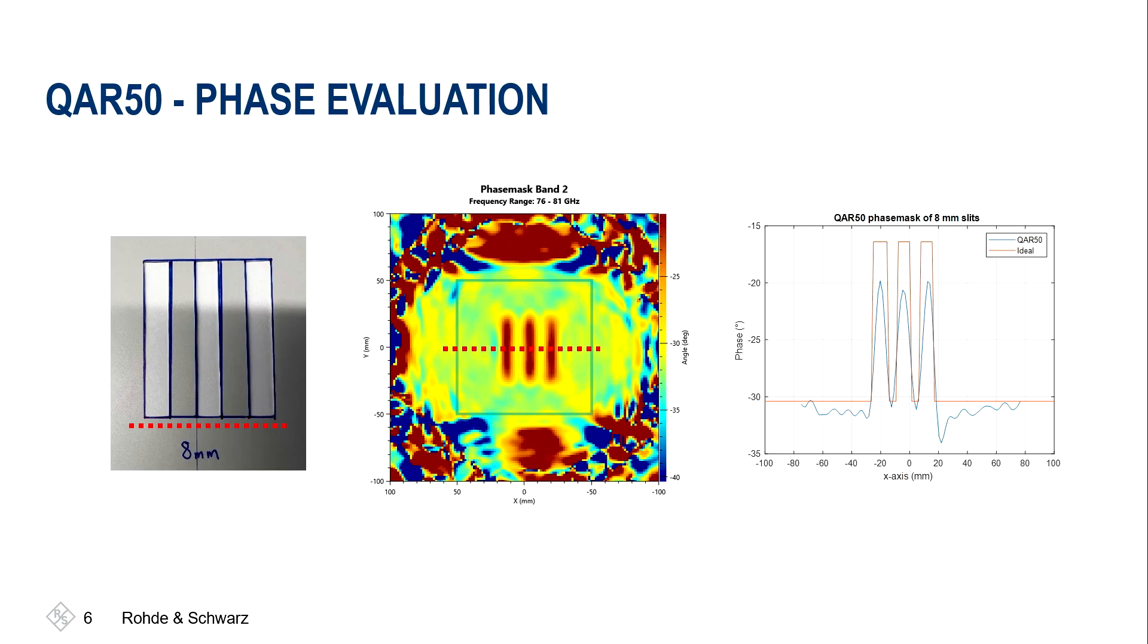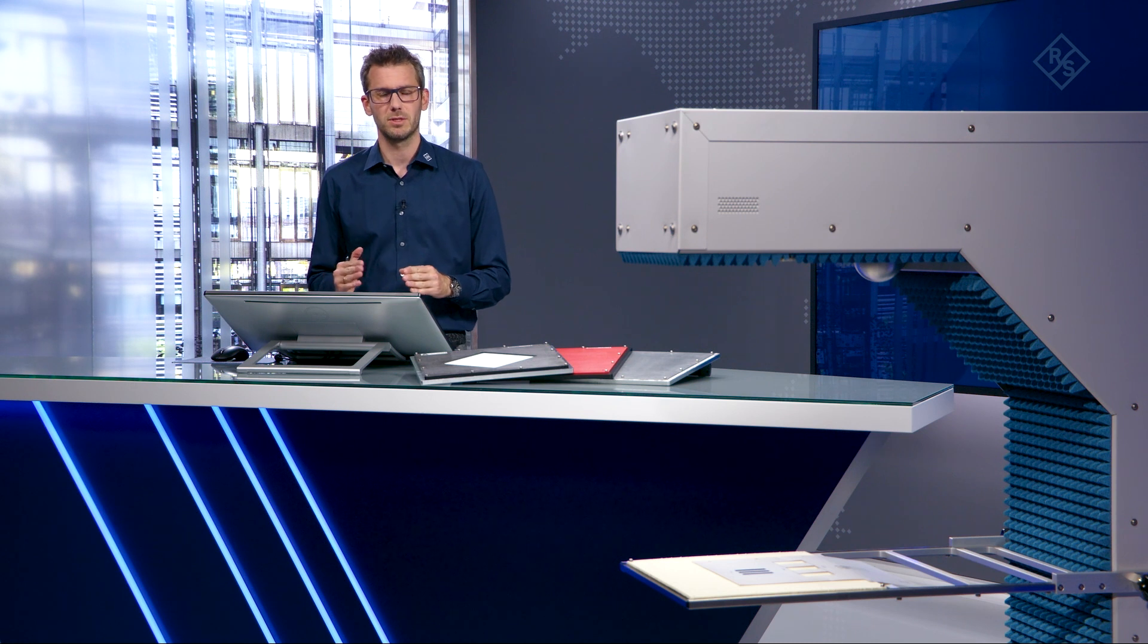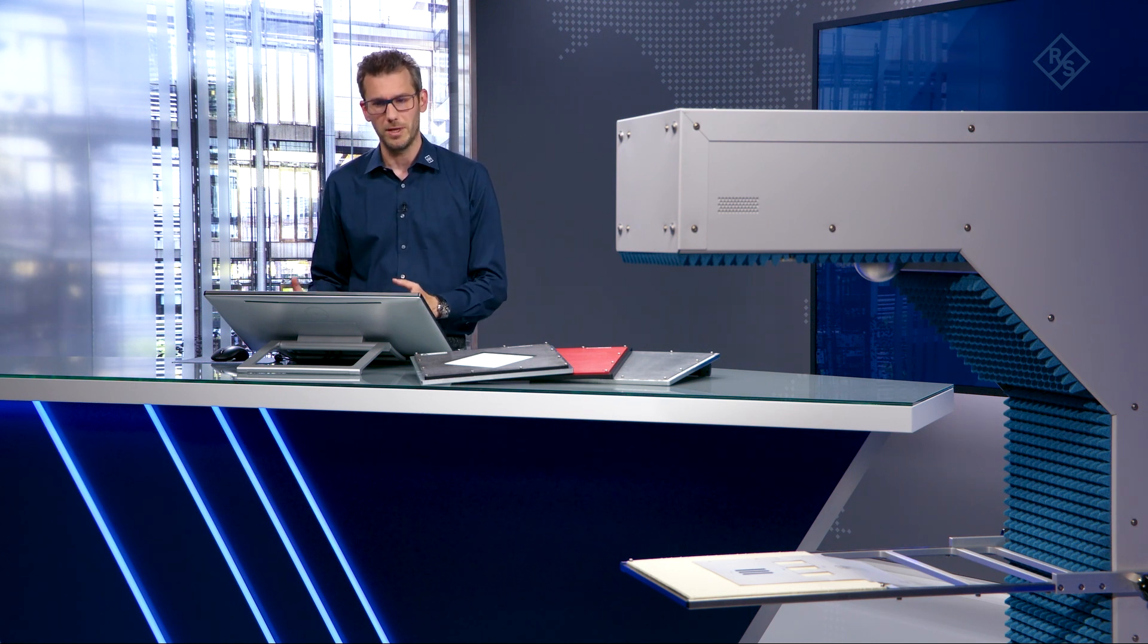If we have a look at this 8 millimeter plate, which is the one currently in the instrument, we can see in the middle of the screen that we can more or less distinguish between the three cutouts. Also on the right hand side, you see the theoretical behavior of the phase and you see what the QAR50 is actually measuring. For this 8 millimeter sample, we can clearly distinguish between these cutouts. And we think this is a worst case scenario for the QAR50. Therefore we stated that the QAR50's resolution is about or better than 8 millimeters.